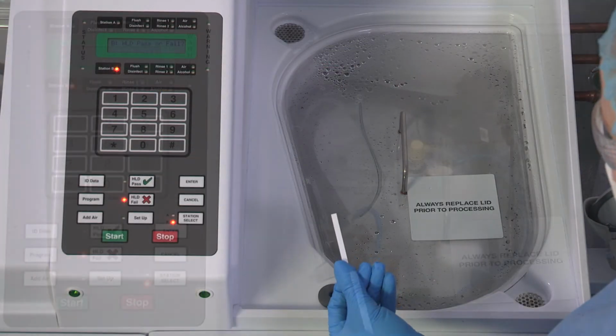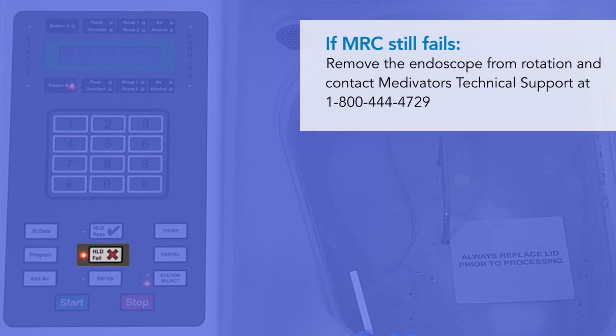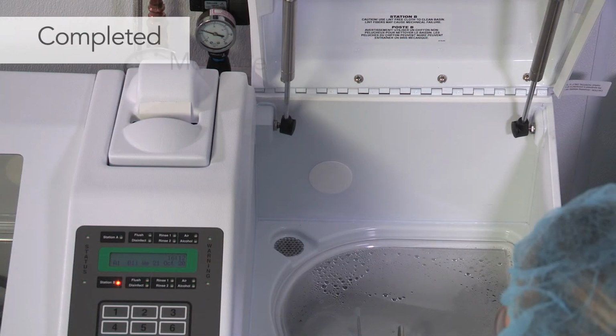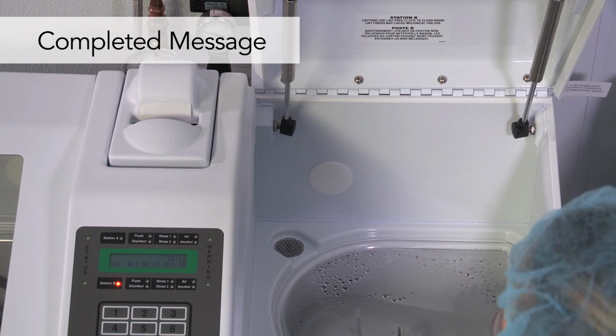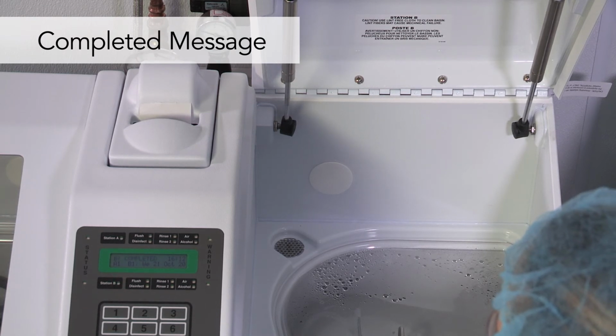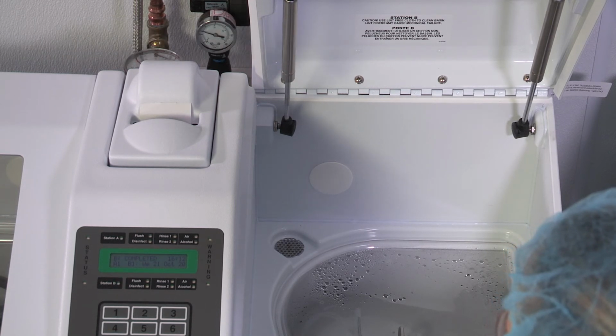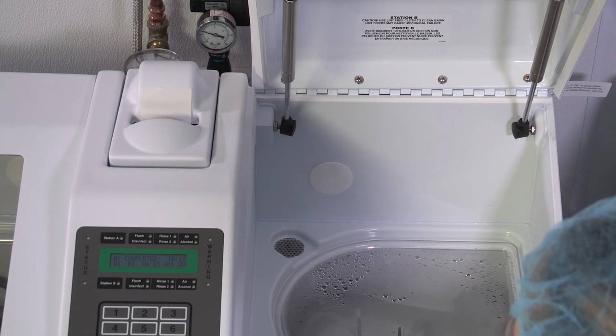If the MRC still fails, press the HLD Fail button. Remove the endoscope from rotation and do not use it for a patient procedure. Call Medivator's technical support at 1-800-444-4729. After 10 seconds, the process indicator light illuminates and the message Completed shows on the display.